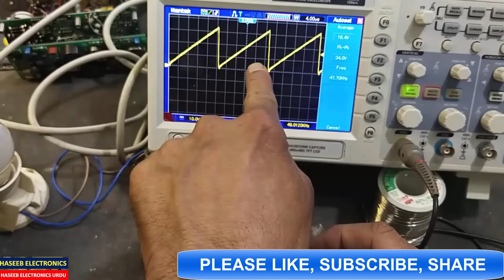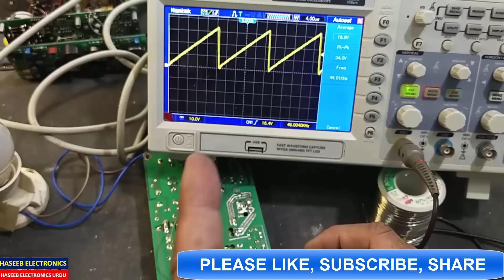Using 1x probe. Here we see 48.1 kilohertz at the CT pin. These are the ramps for RT-CT. So this IC is switching at 48 kilohertz at the CT pin, and when working in push-pull it will divide by 2, so the output pulse must be divided by 2. Yes, it is 24 kilohertz - these output pulses are 23.97, that is 24 kilohertz.